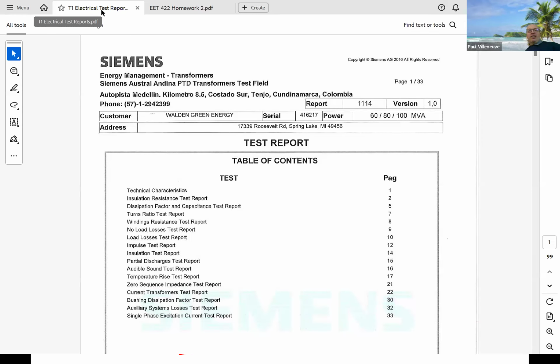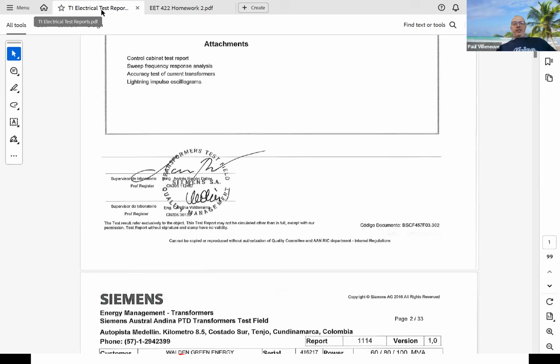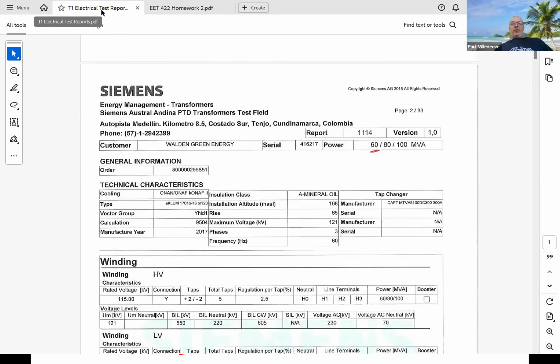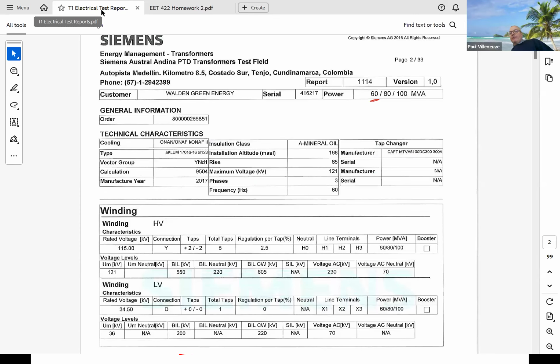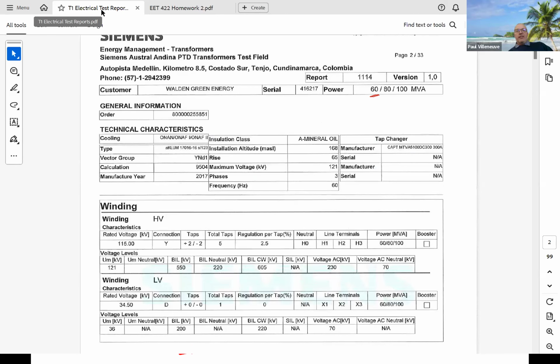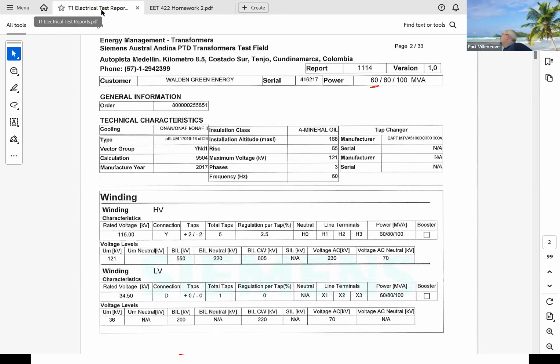Okay. But these other pages have really useful parameters, like the technical characteristics. If you want to learn a little bit about the transformer, this tells you what the details are. So it's got some pretty good stuff identified in here. Okay. Tells you it's a 60, 80, 100 MVA. One of the things about transformers, especially oil-filled transformers, if it's just sitting there, you can see there are fins on it, and that's to help with dumping heat out to the environment. In a transformer this size, they need a lot of help to do it.